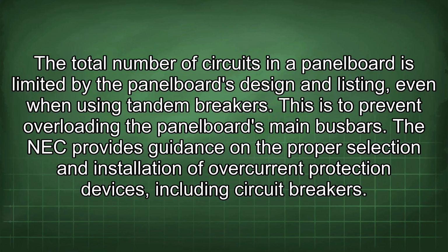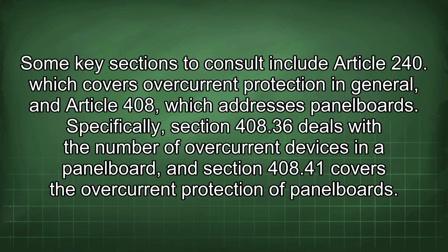The NEC provides guidance on the proper selection and installation of overcurrent protection devices, including circuit breakers. Some key sections to consult include Article 240, which covers overcurrent protection in general, and Article 408, which addresses panel boards. Specifically, Section 408.36 deals with the number of overcurrent devices in a panel board, and Section 408.41 covers the overcurrent protection of panel boards.